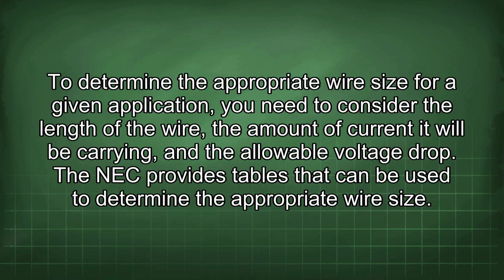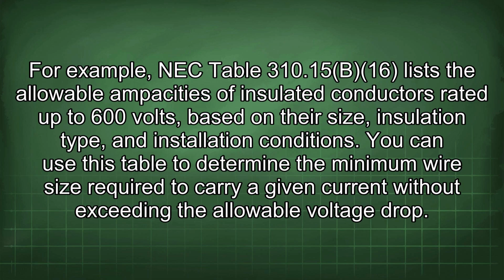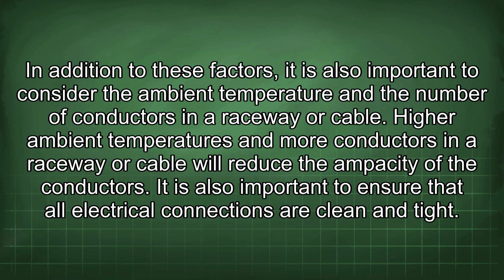To determine the appropriate wire size for a given application, you need to consider the length of the wire, the amount of current it will be carrying, and the allowable voltage drop. The NEC provides tables that can be used to determine the appropriate wire size. For example, NEC Table 310.15(B)(16) lists the allowable ampacities of insulated conductors rated up to 600 volts based on their size, insulation type, and installation conditions. You can use this table to determine the minimum wire size required to carry a given current without exceeding the allowable voltage drop. In addition to these factors, it is also important to consider the ambient temperature and the number of conductors in a raceway or cable.